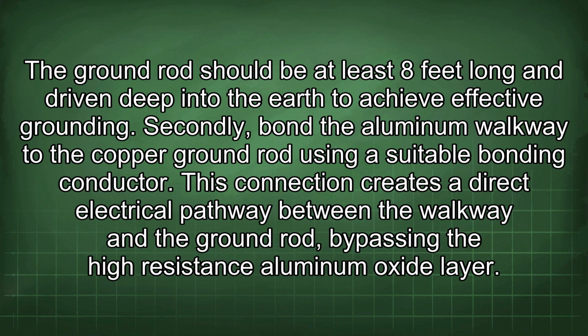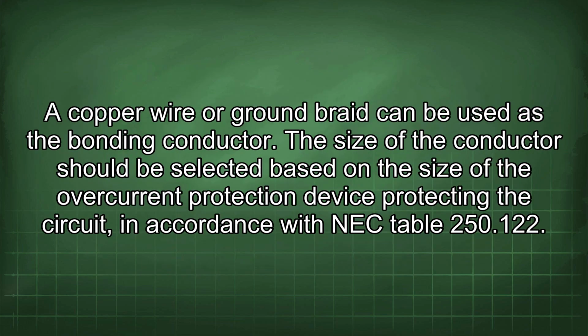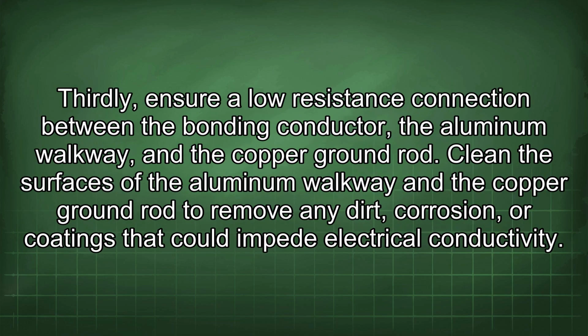Secondly, bond the aluminum walkway to the copper ground rod using a suitable bonding conductor. This connection creates a direct electrical pathway between the walkway and the ground rod, bypassing the high-resistance aluminum oxide layer. A copper wire or ground braid can be used as the bonding conductor. The size of the conductor should be selected based on the size of the overcurrent protection device protecting the circuit, in accordance with NEC Table 250.122. Thirdly, ensure a low-resistance connection between the bonding conductor, the aluminum walkway, and the copper ground rod.